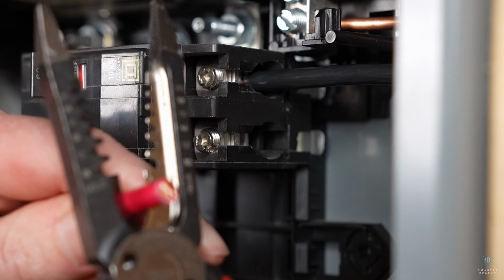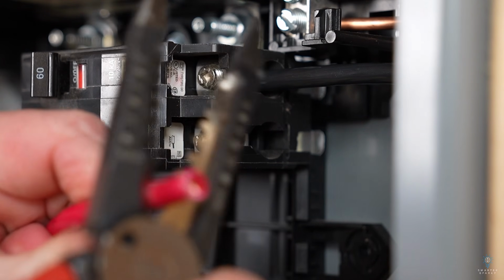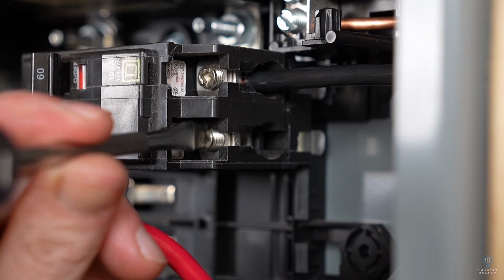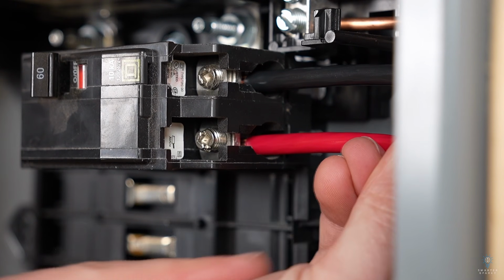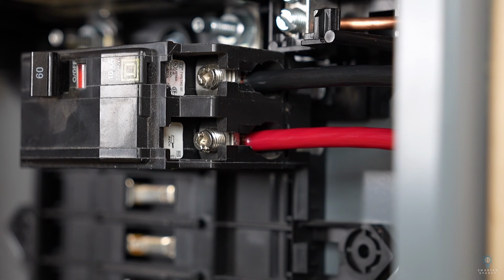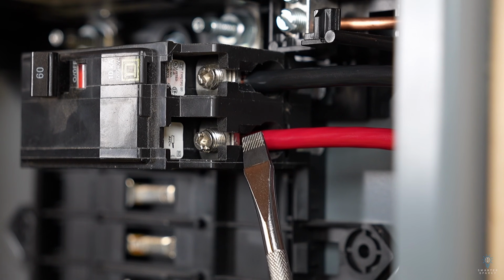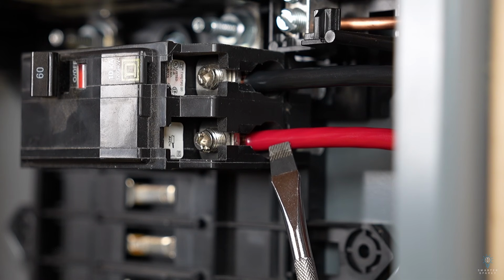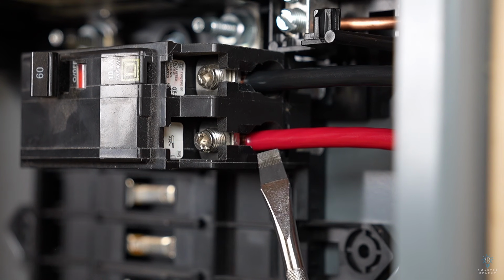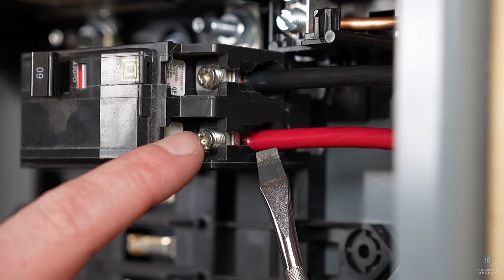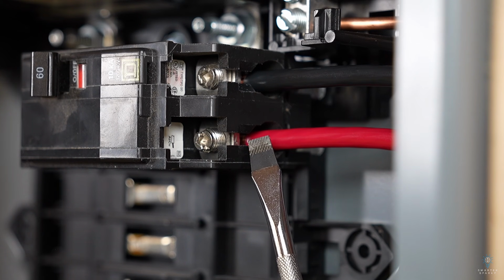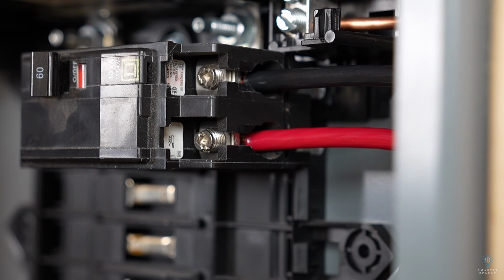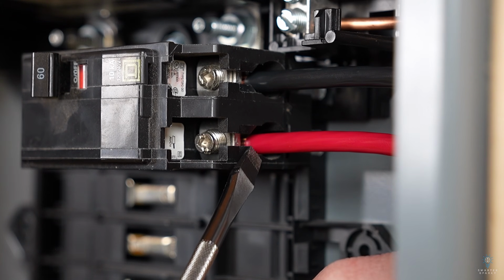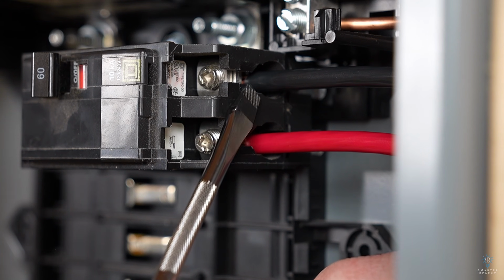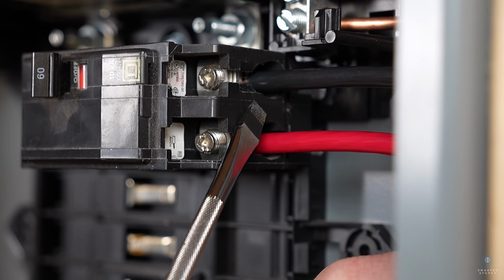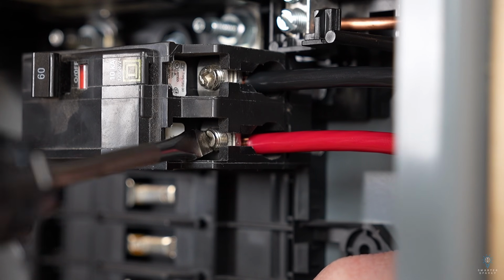Same thing, we strip that out a little bit shorter than everything else we've been doing. Open up our lugs and install like so. Same thing, we should see just the faintest amount of copper on the outside. We do not want any insulation under that lug. If we ever got any of that insulation under that lug, that would create an impedance, which would cause heat, which is why conductors melt sometimes. But we don't want so much copper out that we see bare copper outside the back of the breaker here. So let's go ahead and tighten this lug down.